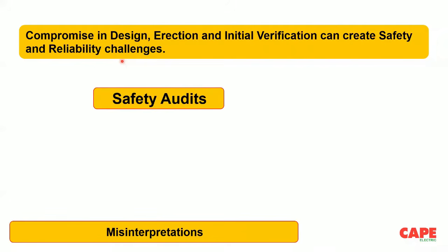Now, to enhance safety, what we do is safety audit. The word safety audit is very interesting to understand. Please note that audit is a checking, sample checking. Sample checking in the sense you have 100 circuits. You check three circuits on a sample basis and you make an audit. Or you check 10 circuits and you make a safety audit. This actually is illegal as per the standard. The IEC standards never use the word, or very, very rarely use the word safety audit. The word which is used in the standards is always verification.